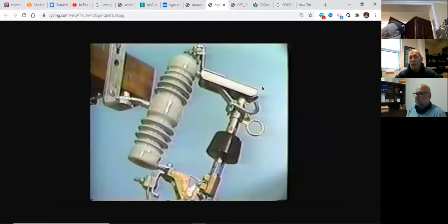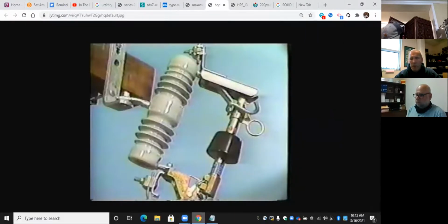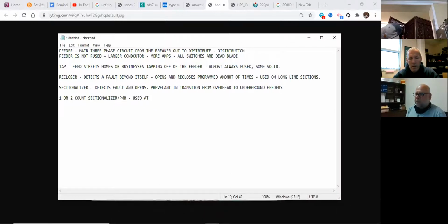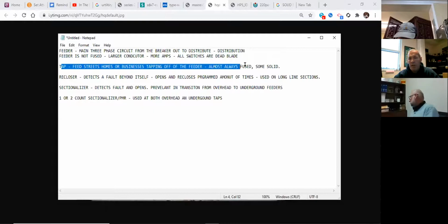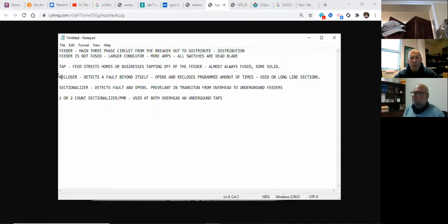Let me get down to here. I want to put this in clear - used at both overhead and underground. I'm going to put this in here: taps. Okay, so we're out of the feeder now - a feeder breaker, that's where we were. Tap - we included this just to give you the definition of a tap. Reclosers are in the feeder, sectionalizers in line with the feeder, and now we're moving on to taps and tapping off the feeder, used at both overhead and underground.